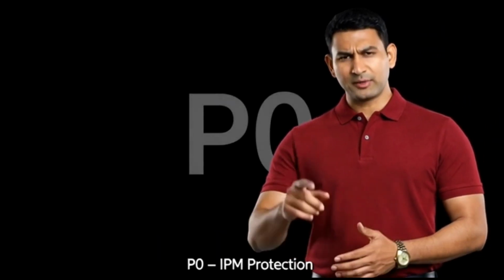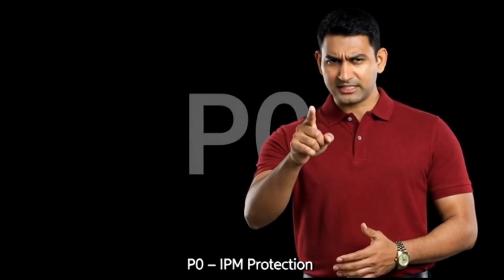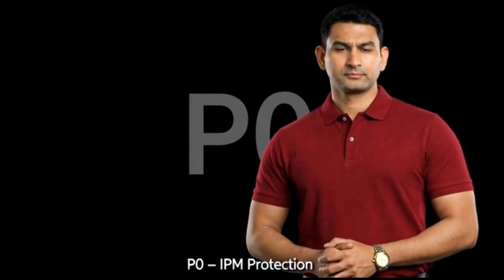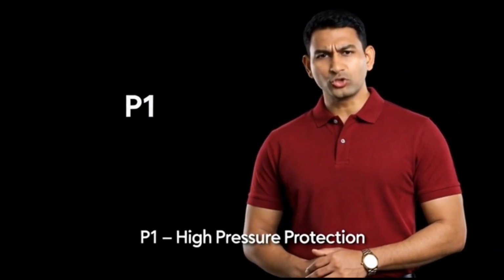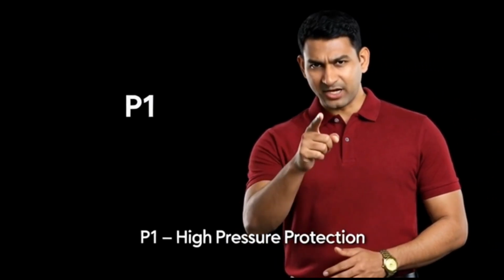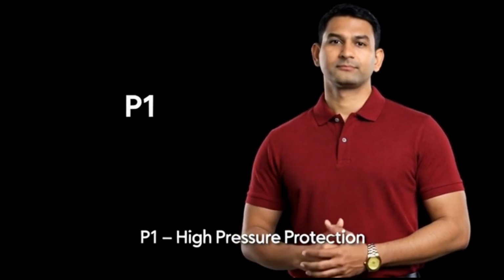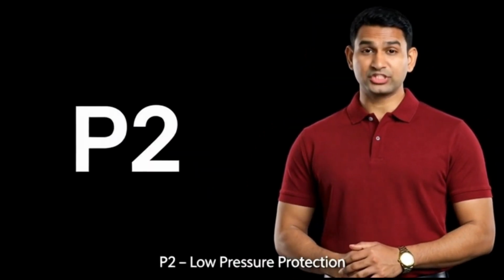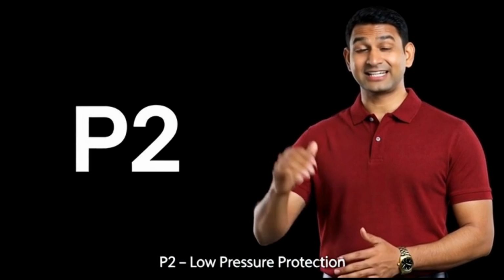P0 error shows inverter module protection is active. Check PCB and connections. P1 error occurs due to high refrigerant pressure. Inspect condenser and airflow. P2 error indicates low refrigerant pressure. Check gas level and leaks.